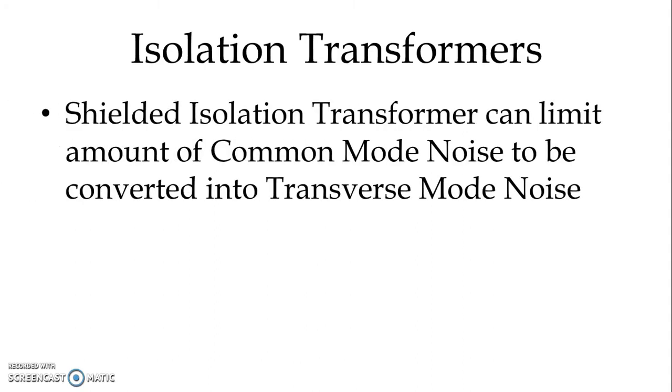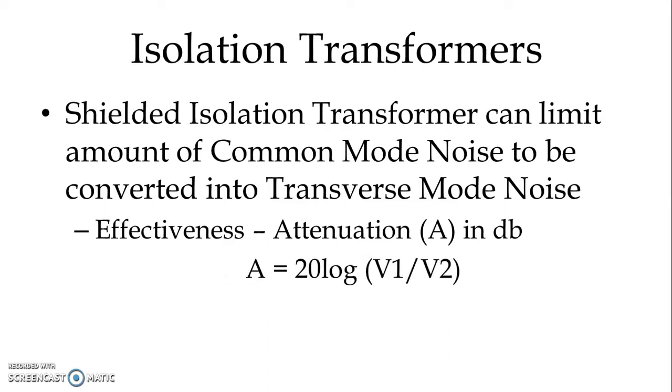Shielded isolation transformers can limit the amount of common mode noise to be converted into transverse mode noise. The effectiveness with which a transformer limits common mode noise is called attenuation and it is indicated in decibels. We can write A = 20log(V1/V2), where V1 is the common mode noise voltage at the transformer primary and V2 is the differential mode noise at the transformer secondary.